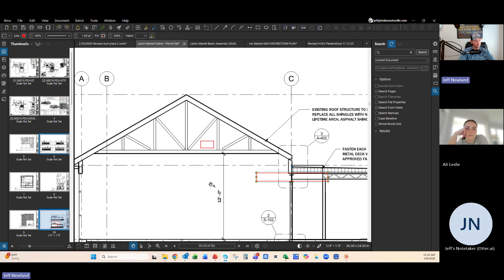All right, equipment set, AHU, RTU, exhaust fans installed. So how do we get those exhaust fans on the roof? How do we get those RTUs on the roof? Unless it's an exhaust fan, you could probably get up with a lull, depending on your ceiling height. But a big RTU unit, you're going to want to get up there with a crane. So you just need to make sure that's included in your HVAC, and your estimator should have done that too. But you need to make sure that the crane, or the means by which they intend on getting that equipment on the roof, is actually bought out. Mm-hmm.